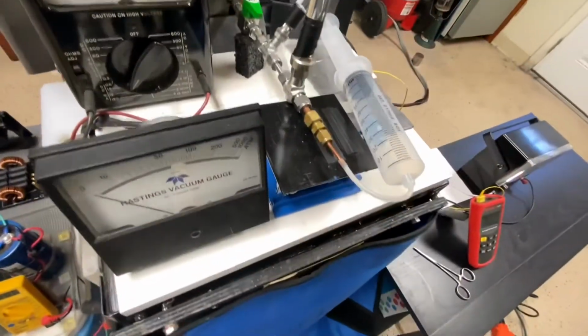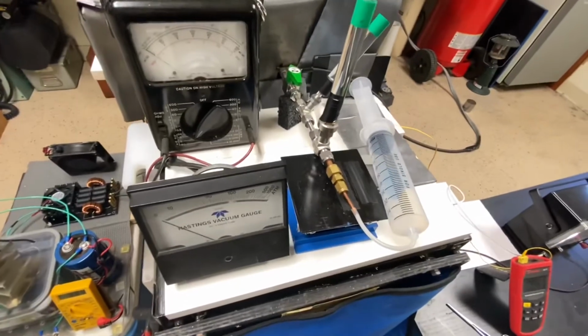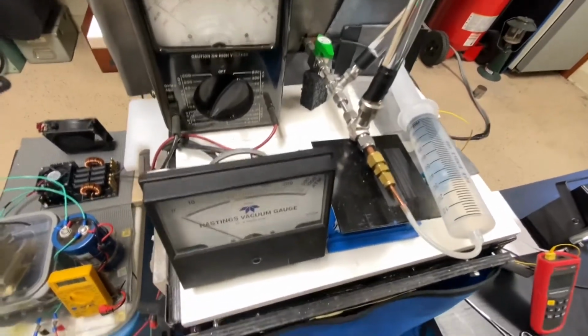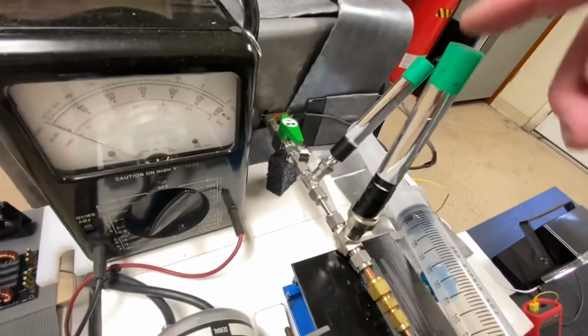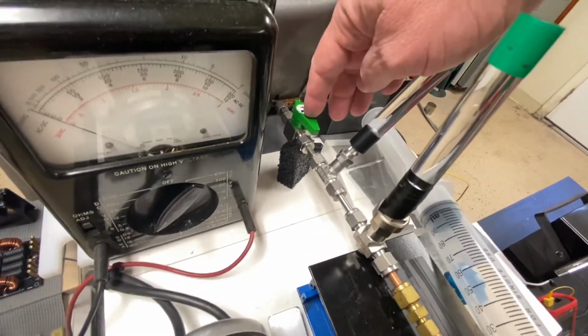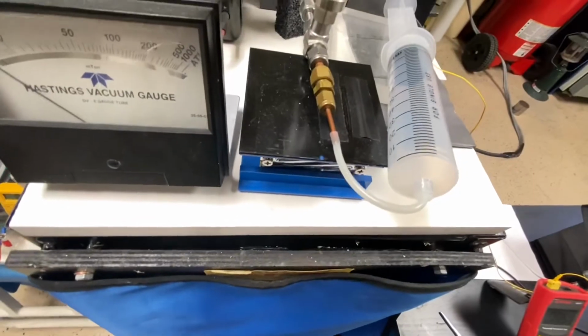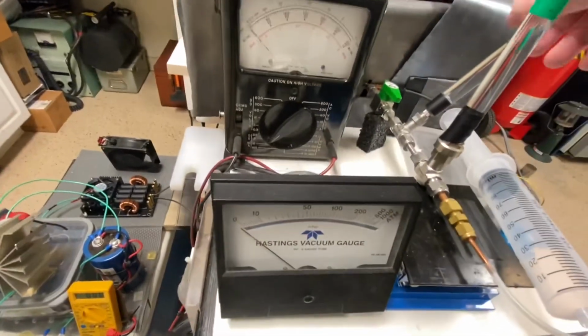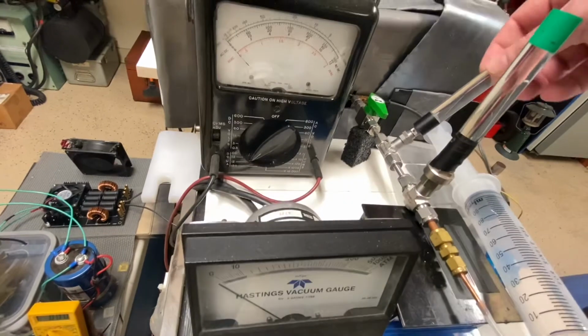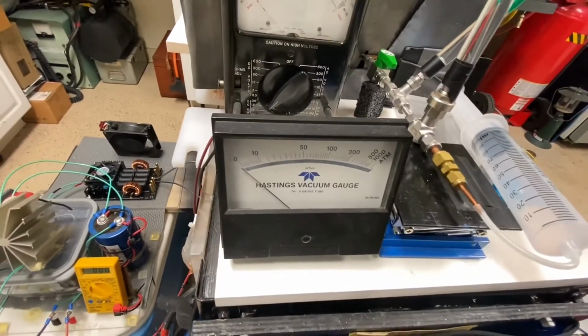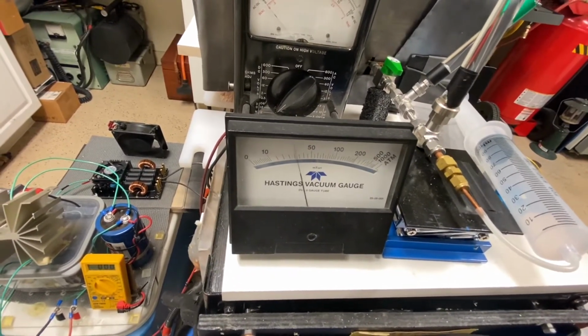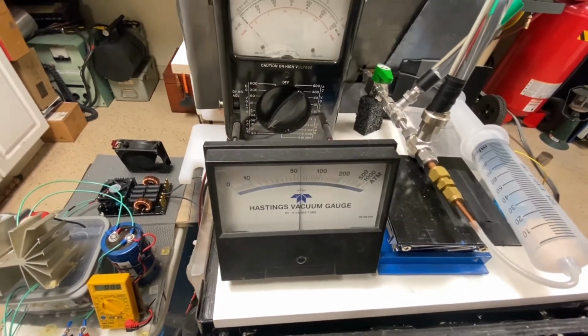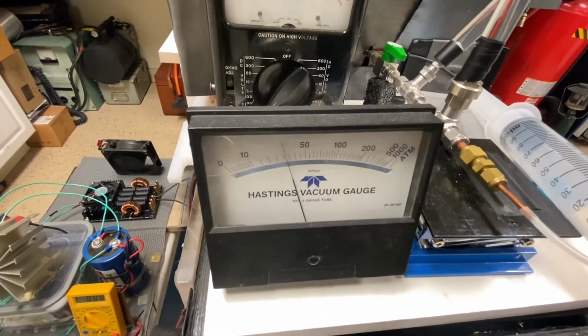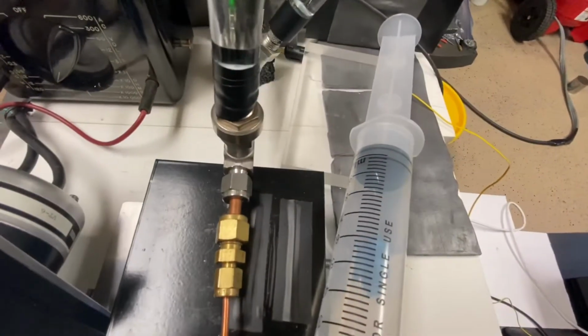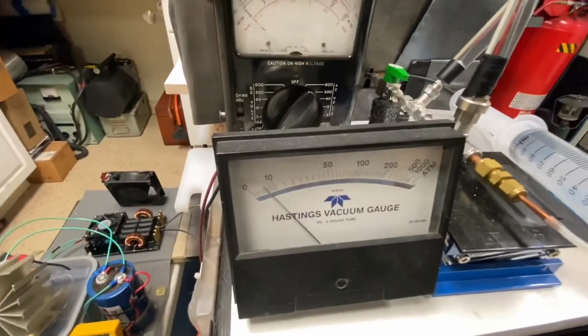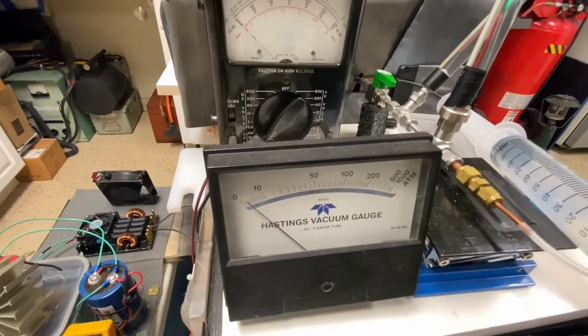All right, so I actually skipped over one part that's kind of important. You want to prime the system with fresh deuterium before you get it set up. So you turn off your needle valves, keep your gate valve open, and remove the hemostat. You're still at 0, so what you want to do is set your valves and prime the system. Just let it shoot up to about 50 or 80 millitorr a couple of times. You can see you're not using hardly any gas, so it's not really a waste. It's just very small because they are needle valves. Okay, I usually do it twice.